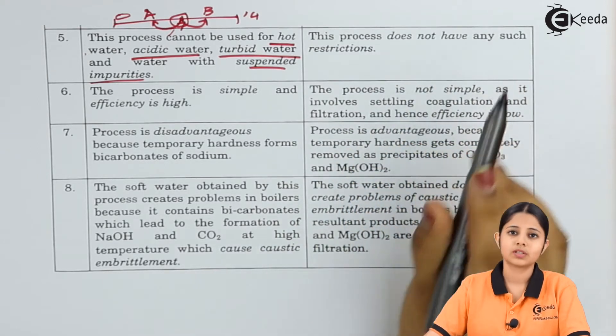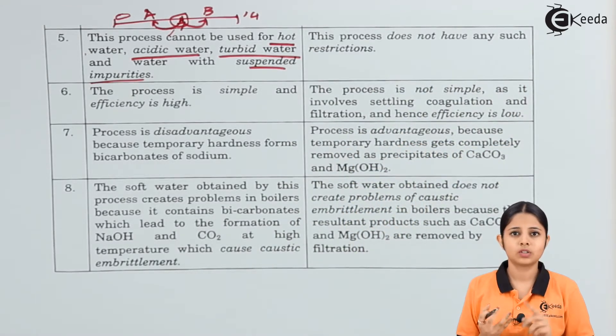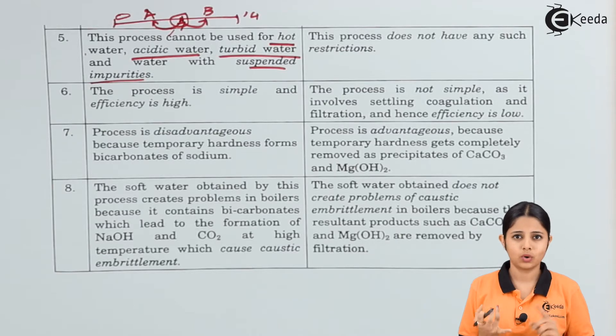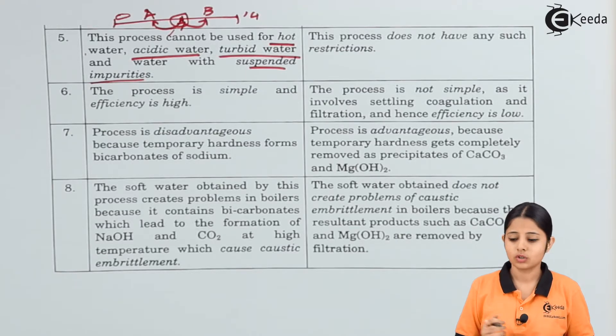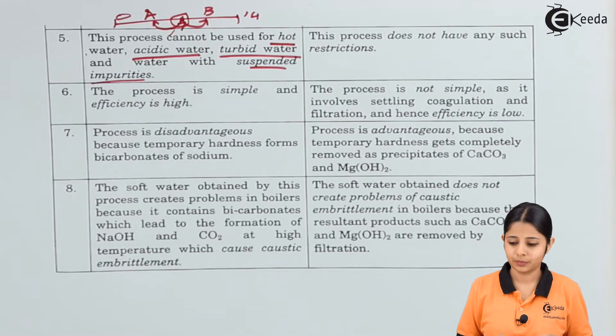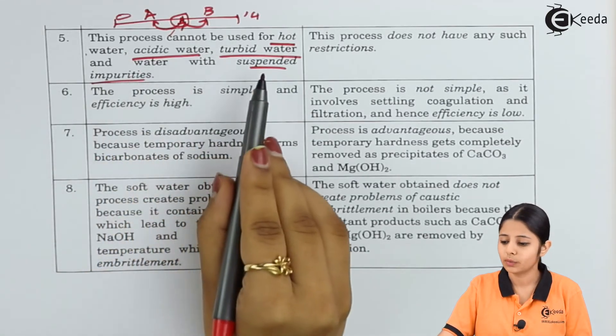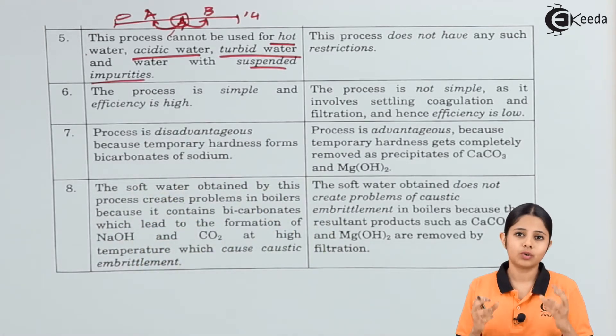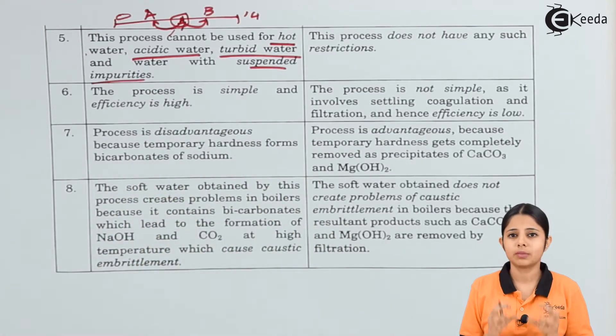The lime soda process does not have any such restrictions. Lime and soda are not extremely reactive in hot water — in fact they react better at higher temperatures. The lime soda process also has no issues with acidic water, turbid water, or suspended impurities. So depending on the type of water and impurities present, the appropriate process can be chosen.